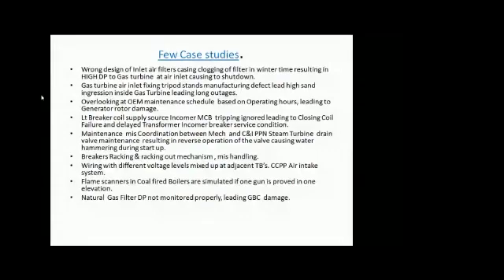Coming to the overlooking of OEM maintenance schedules. OEMs prescribe operating hours, after which you have to do some inspection or maintenance. All those things they mention. Those things should not be overlooked, because it is going to create huge damage. In one power plant, because they wanted to show that they are running the plant and able to generate power, high PLF, huge generation, they had a very bad intention of running the power plant by overlooking the OEM schedule. This has caused damage to the generator rotor.